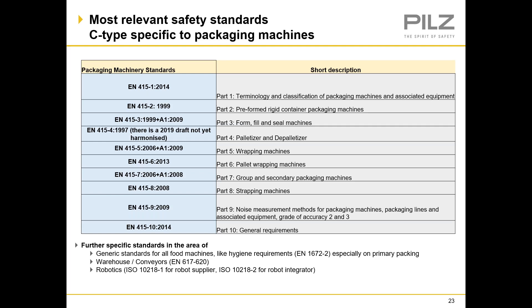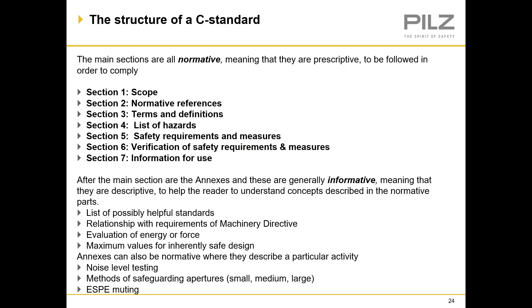Parts 2 and 4 of EN 415 were both released in the late 1990s and are not harmonized or designated to either the machinery directive or annex 1 of the supply machinery safety regulations, though it's recommended they are still used where relevant. The structure of a standard: section 1 is scope, section 2 is normative references, section 3 is terms and definitions, section 4 is a list of hazards — you still need to conduct your own risk assessment — section 5 is safety requirements and measures, section 6 is verification, and section 7 is information for use. Annexes are generally informative.